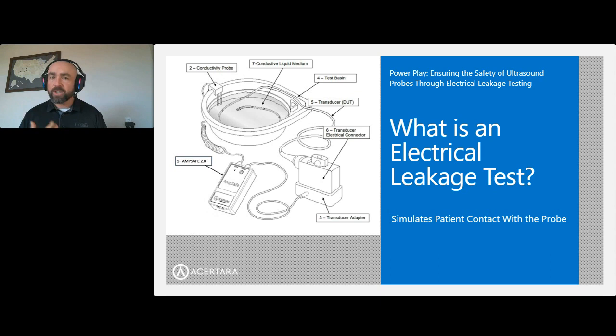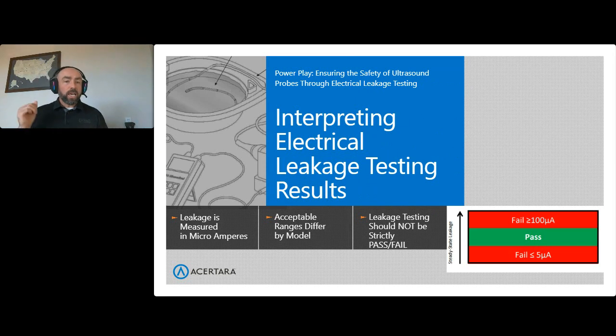Again, make sure that your device actually has the specific limits for the transducer that you're testing. Otherwise, you're kind of wasting your time here. So leakage is measured in microamps, and it tends to be used with a method that is safe for you to use. The device that we manufacture, as an example, has a 500 microamp limit. So if the device measures above 500 microamps, it cuts out. So if you had your finger in the water, you would be safe. I still don't recommend that you do that.